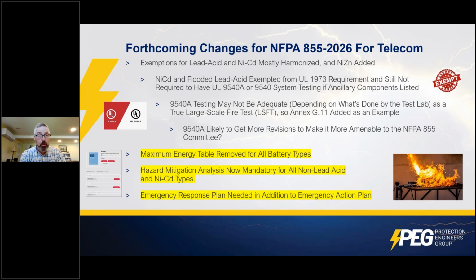There's a push to get more benefit out of UL listings for batteries. There are VRLA batteries that are UL 1973 listed, and we want to take advantage of that and get some additional exemptions from some of the requirements when those are in place. However, we realized that NiCad and flooded lead acid batteries aren't yet available UL 1973 listed. They were never required to be listed before, and they're not in the marketplace now. So we've brought in the exemptions to actually allow for either listed UL 1973 regulated lead acid batteries to have exemptions, or flooded cells or NiCad cells. So it's good. As part of broadening those exemptions, we've addressed the fact that some technologies aren't yet available listed, even though ideally everything would be listed at some time in the future.